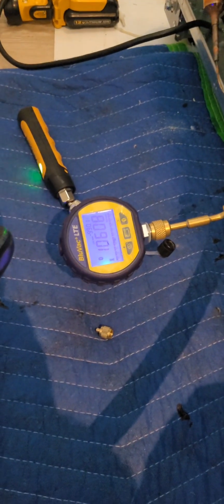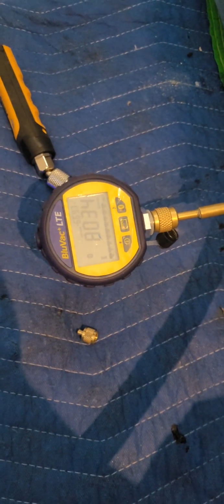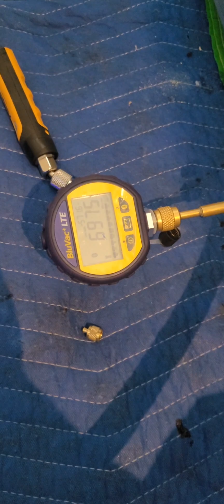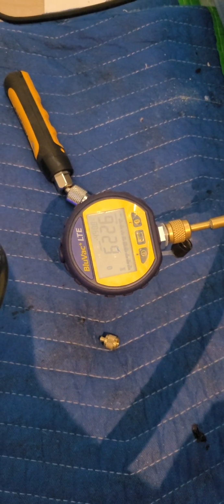Okay, so our pressure test passed. Now we're getting into our evacuation. We got our blue vac light on there. It's pulling down, so we'll wait till we're just below 2,000 microns, and we'll close in our gas ballast on our Fieldpiece pump.